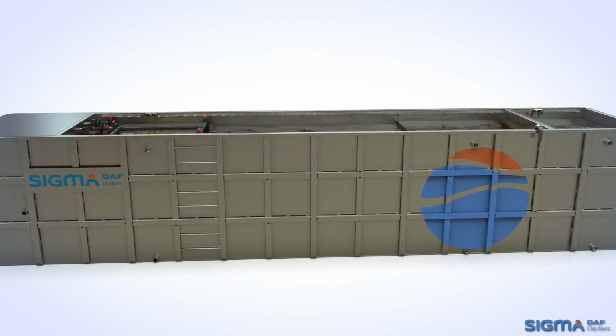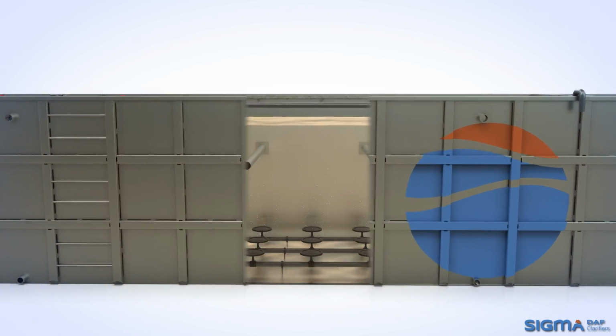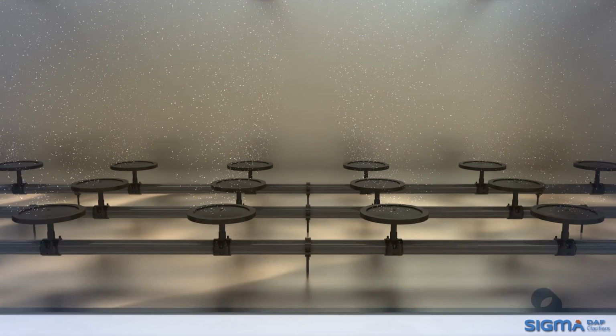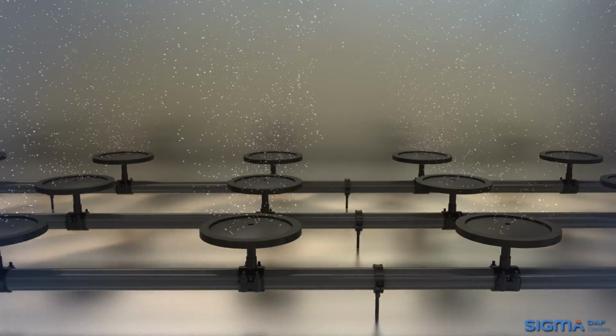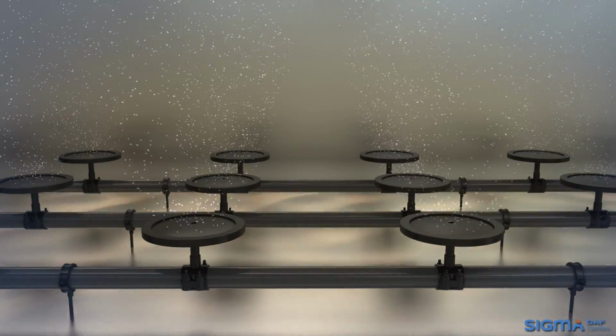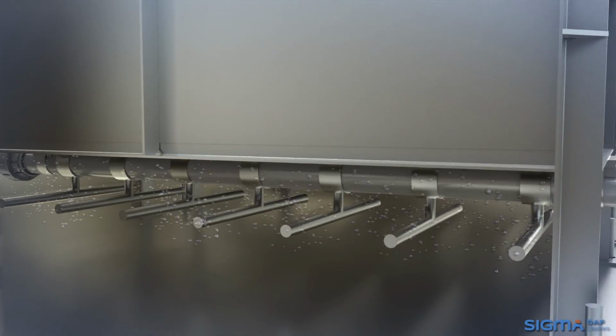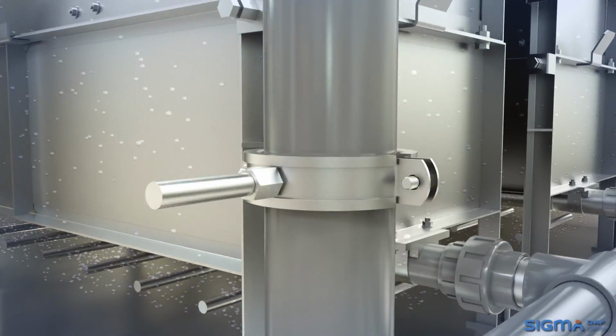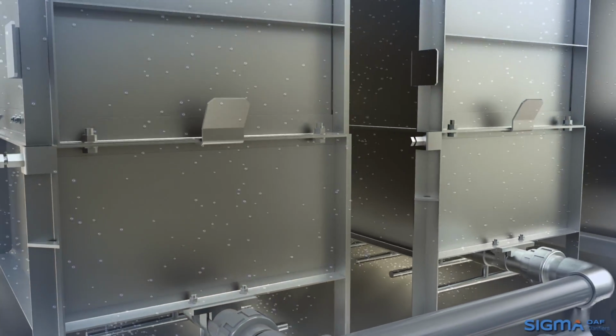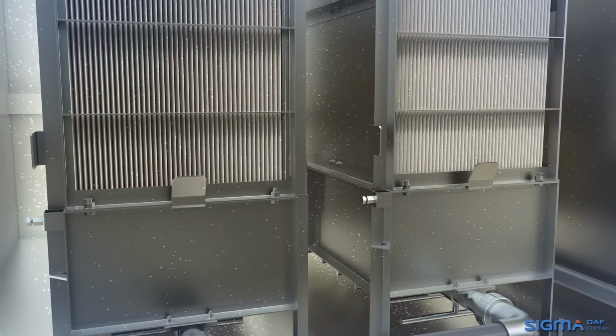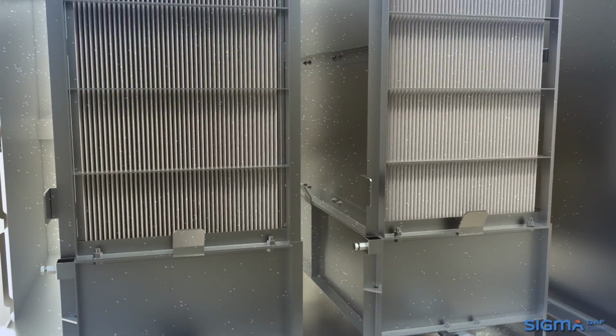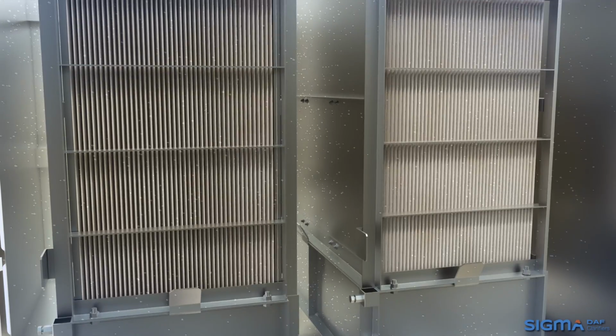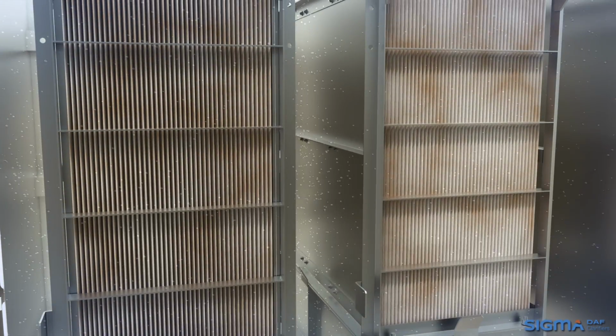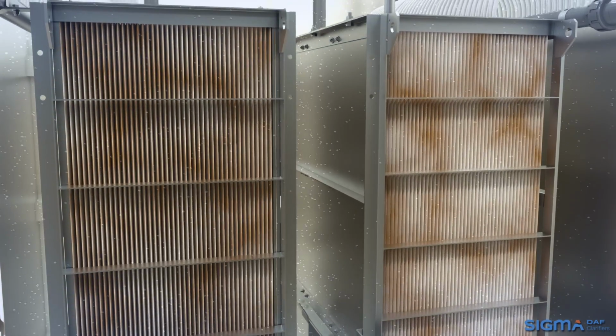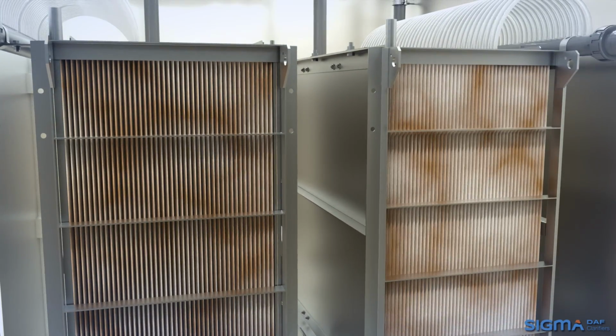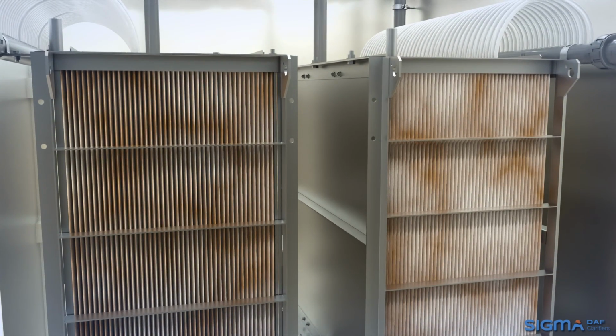Subsequently, water moves from the anoxic zone to the MBR reactor through communicating vessels, being aerated by a blower and fine bubble diffusers and then filtered through submerged membranes. At the bottom of the membranes, another bottom-to-top aeration occurs as a preventive cleaning step and is part of the filtration process. The MBR reactor degrades organic matter, COD, BOD5, and suspended solids through biological reactions facilitated by the present biomass and physical reactions facilitated by the submerged membranes.